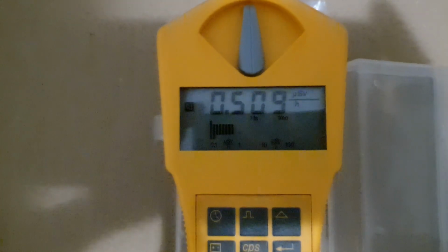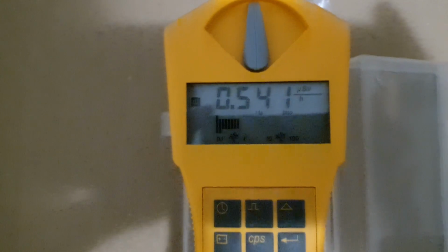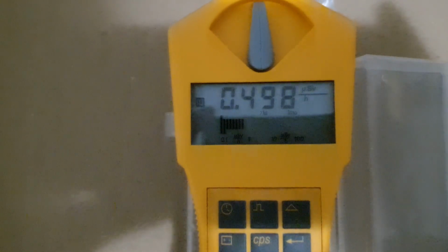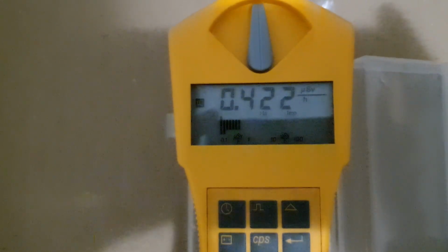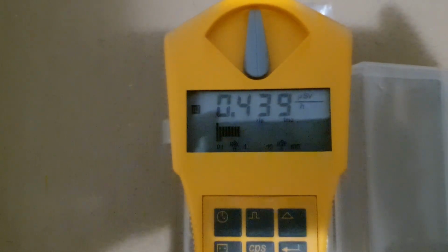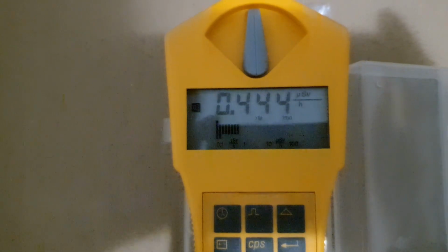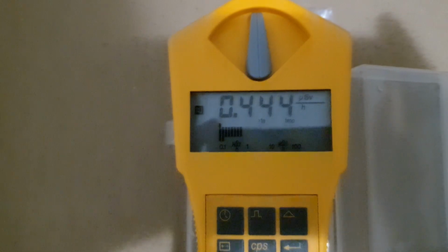A dose rate between 0.42 and 0.54 microsievert per hour was measured at the distance previously determined using the Cesium-137 source. We can assume a maximum error of plus 125%, which is not compliant with the normative requirements. The dose rate overestimation was expected, as the Geiger tube is uncompensated for energy.